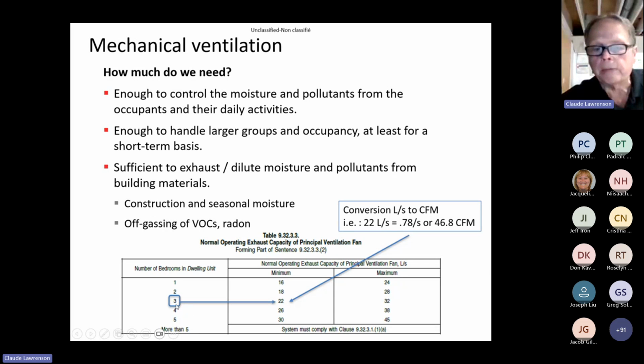So we have 3 bedrooms on the average 3-bedroom home. That talks about the ventilation rates, okay, a minimum of 22, and 22 is liters per second. But if we convert that to what some of us understand as CFM, that equates to 46.8 or roughly a 50 CFM fan. Typically, you would find something like that in the 40 to 50 range in a bathroom exhaust fan.